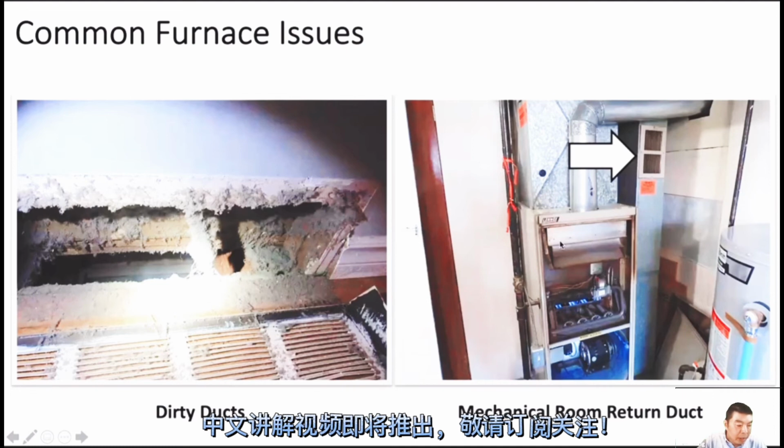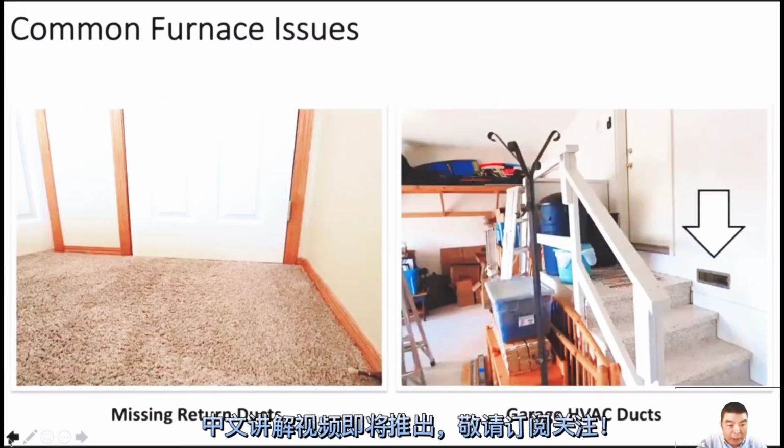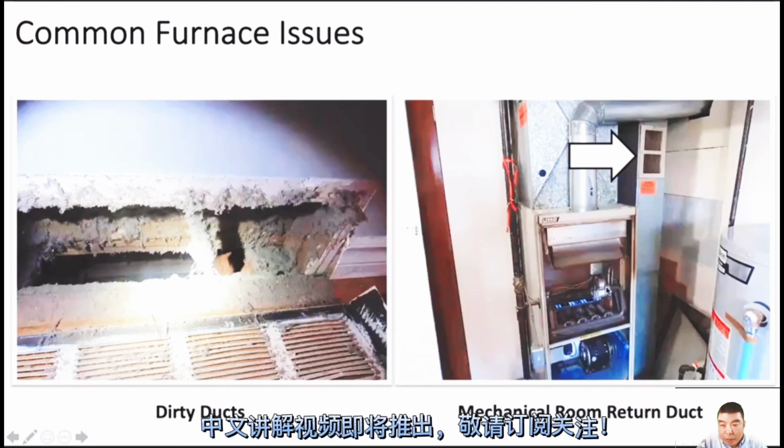Here you can see the pilot flame. For a furnace like this, we can see the gas valve. There's a small aluminum pipe that comes out from the gas valve here and goes inside, under the burner here. This one we call the standing pilot.